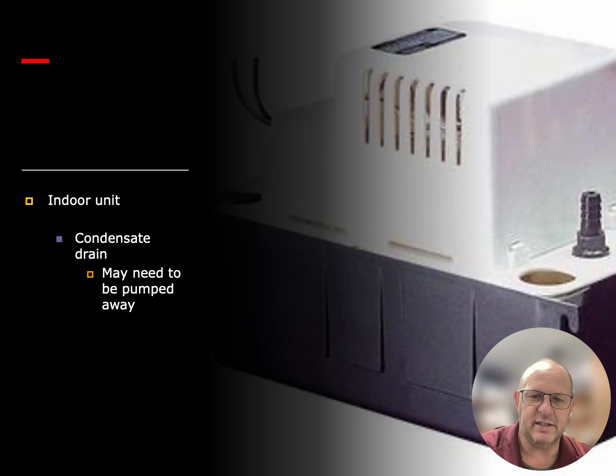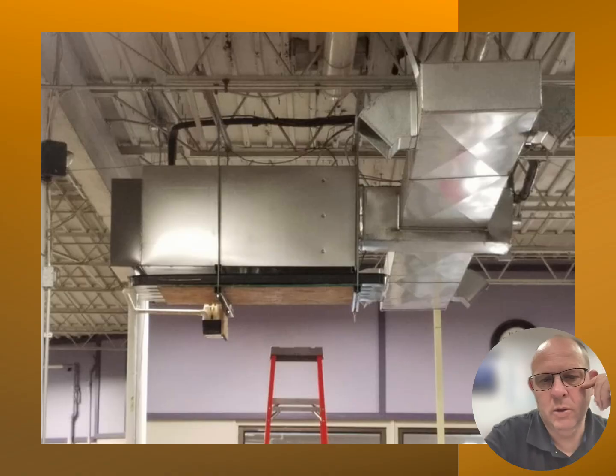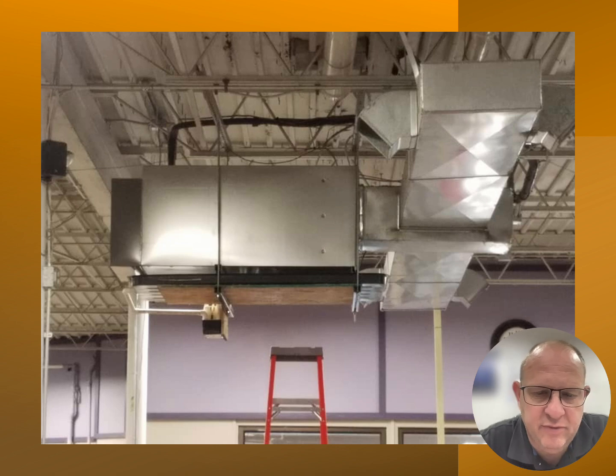So here's an installation that I have done at a local thrift store. A couple of things I want you to notice: the ductwork is nice and straight. The condensate drain that we have put on there is going to be pumping the condensate from the indoor unit out into the outside, in a place where it's going to drain away relatively easily without causing any damage. But one thing I want you to pay particularly close attention to is the auxiliary drain pan that's underneath this particular unit. This drain pan was there for the purpose of catching overflow of the condensate if it was ever to plug up the main drain on the top portion of it.